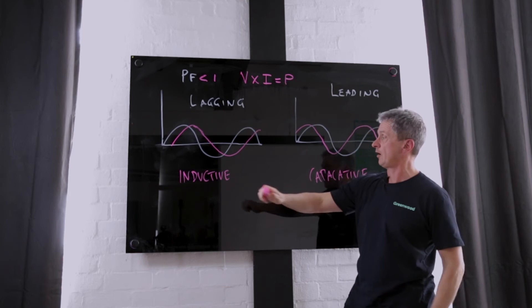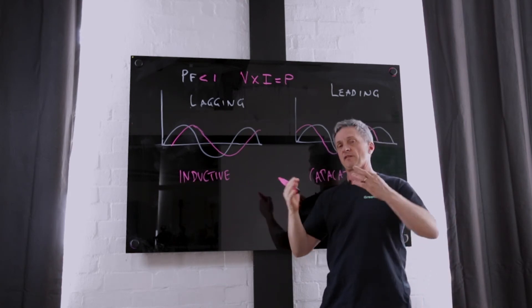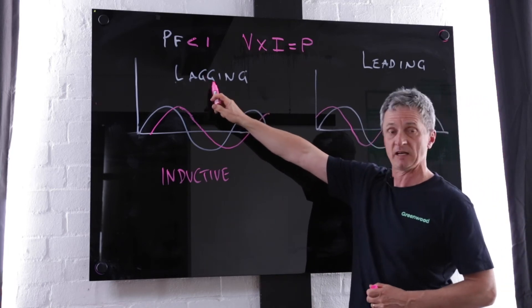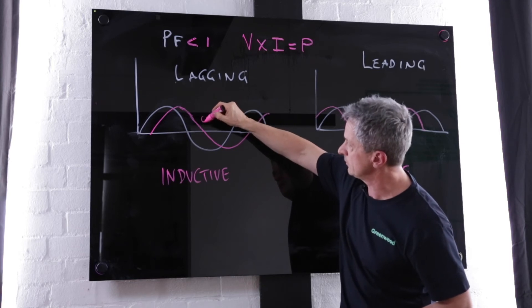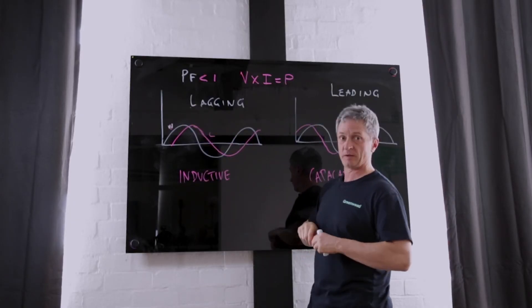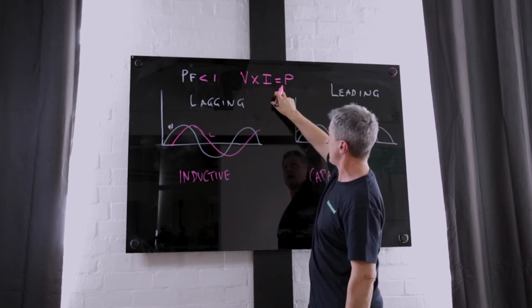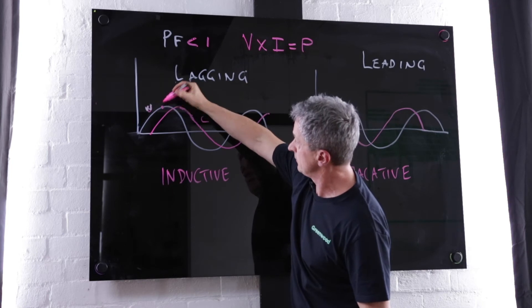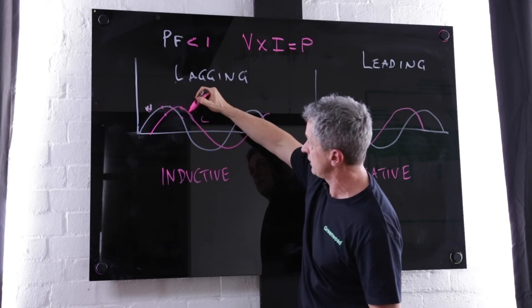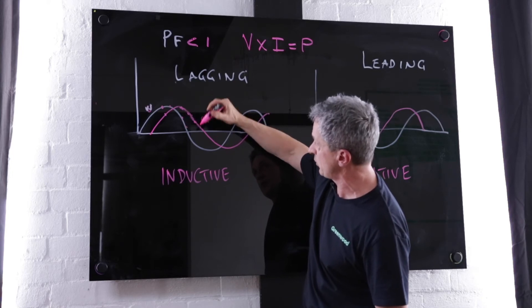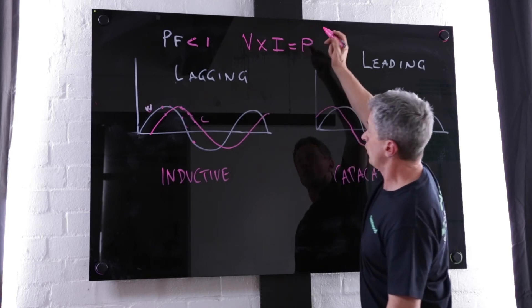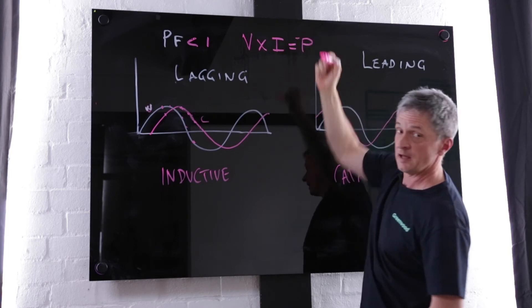In the case of a site with a lot of inductive loads — for instance, an engineering company with lots of three-phase motors — we have a lagging power factor. That means current is lagging the voltage. Now if we apply the principle of V times I equals power, we can see at certain points voltage times current is positive, but look when we get to this point here: voltage is negative, current is positive. That means we have negative power, and that's the reactive power.